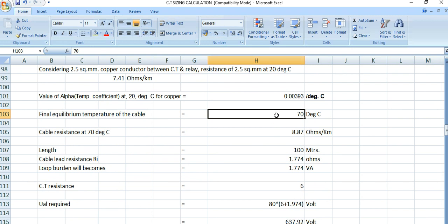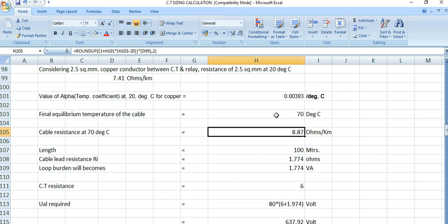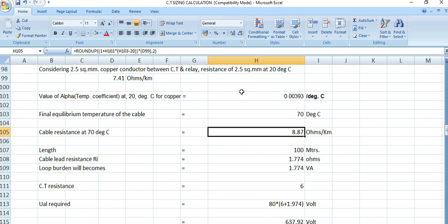Using the formula: 1 plus alpha into (T2 minus T1), that is 1 plus 0.00393 into (70 minus 20), multiplied by 7.41 ohms/km, this gives 8.87 ohms per km — the cable resistance at 70°C.